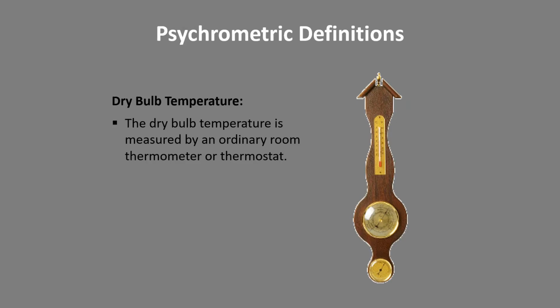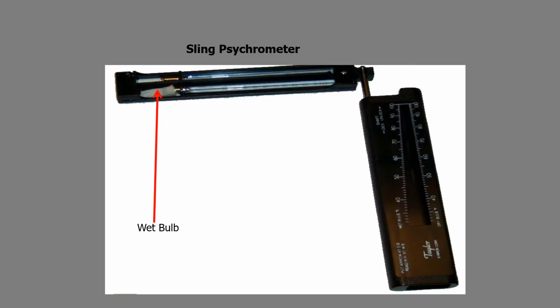Some psychrometric definitions. Dry bulb temperature is the temperature measured by an ordinary room thermometer. It's also what the thermostat reads. This is sort of an old school non-digital psychrometer. You've got two thermometers in here, if you will. You have a dry bulb one and you have a wet bulb one. And there's a little cotton sock here and a water reservoir here.